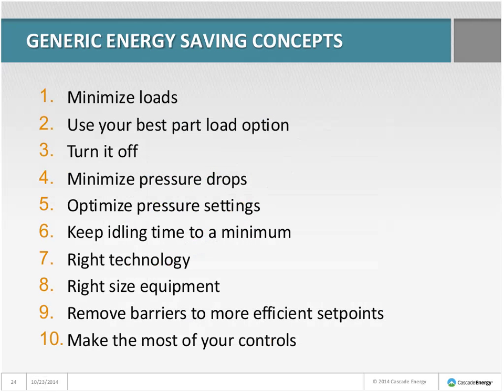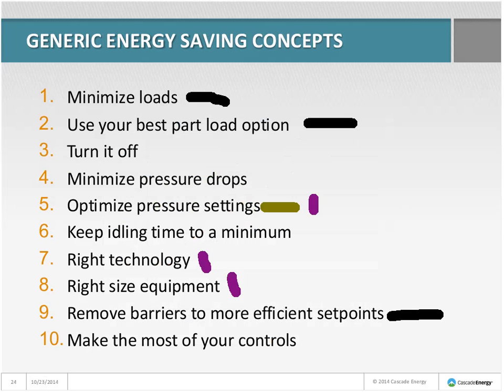Thinking back to the 30-horse compressor running a palletizer: what did these guys do to save energy? Definitely number two — use your best part-load option. The compressor already had load-unload control; they just needed to use it. And number five — optimize the pressure settings. They didn't need 129-PSI air; they just needed to keep it above 90. And number ten — make the most of your controls.